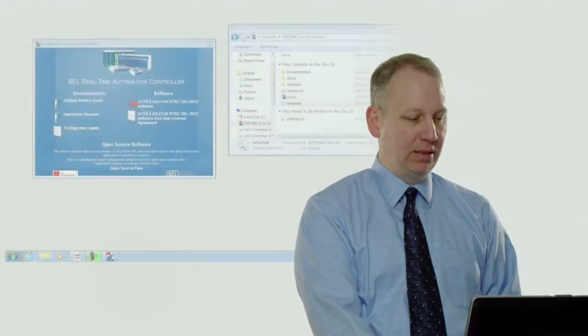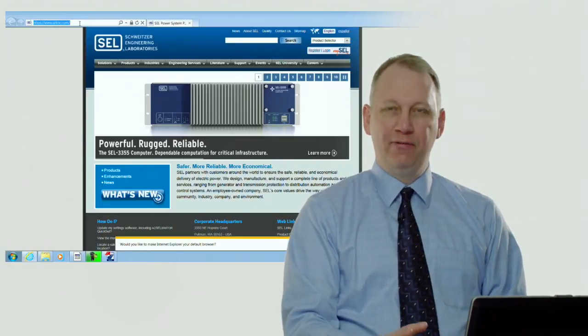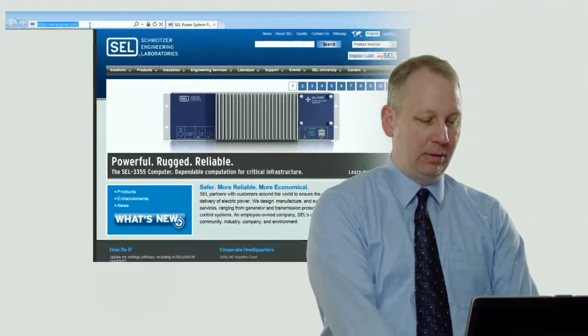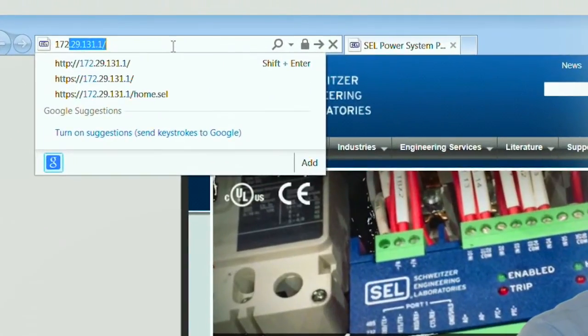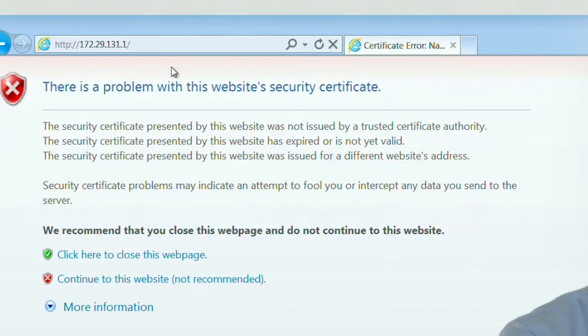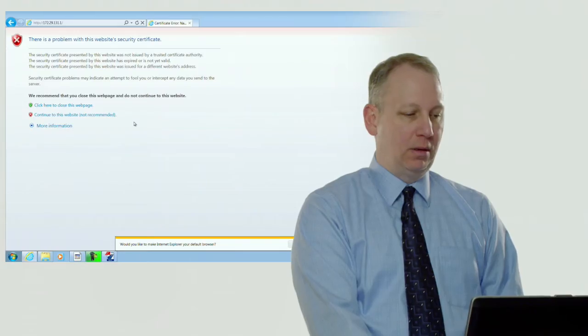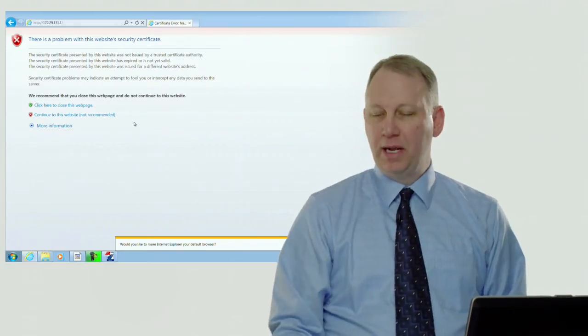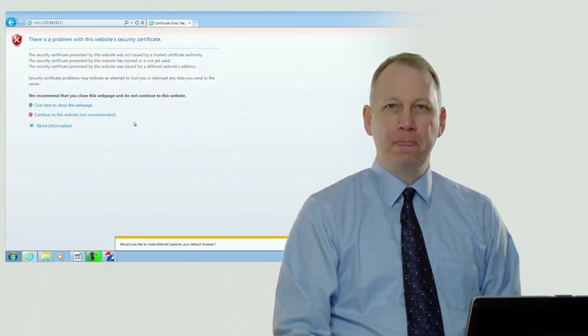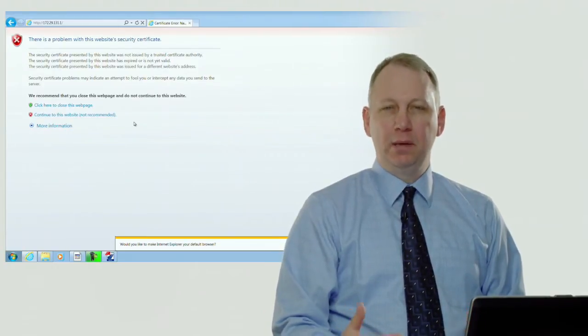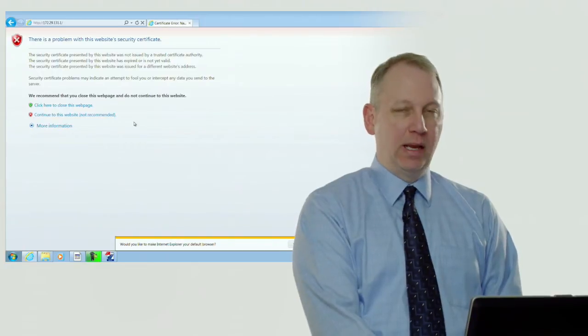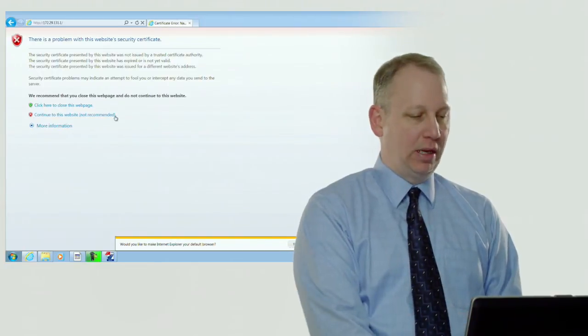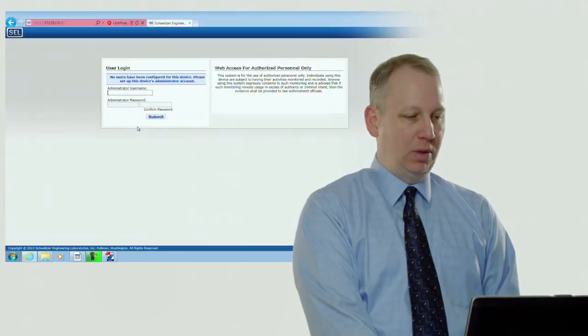After the software is complete, we're going to open up a web interface. There's an IP address that is now fixed to be used with this USB-B cable. The IP address is 172.29.131.1, so enter that into the browser. You're going to notice there's a security error. What that's all about is the RTAC has an X.509 certificate that's built in but it's not signed because it's just fresh out of the box.